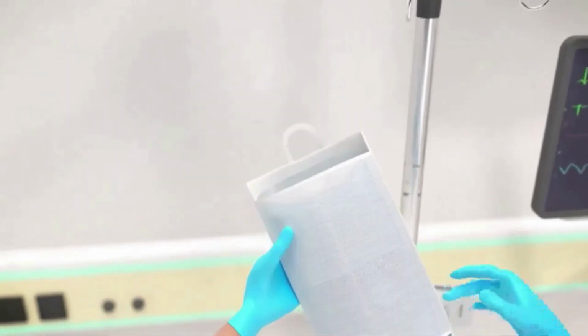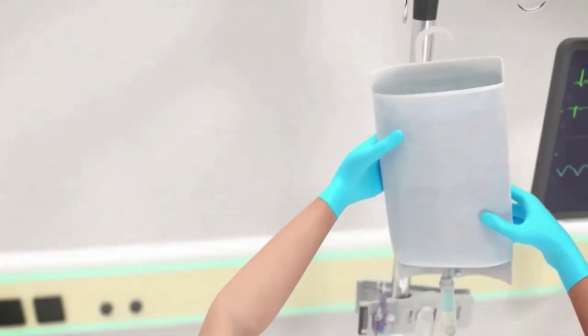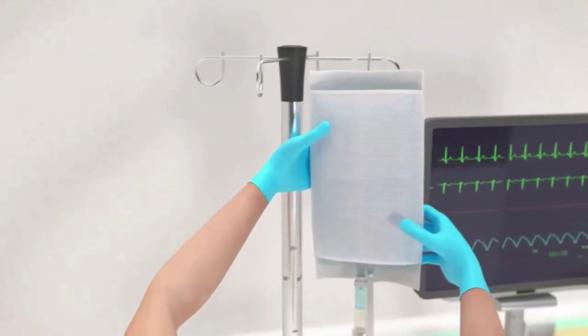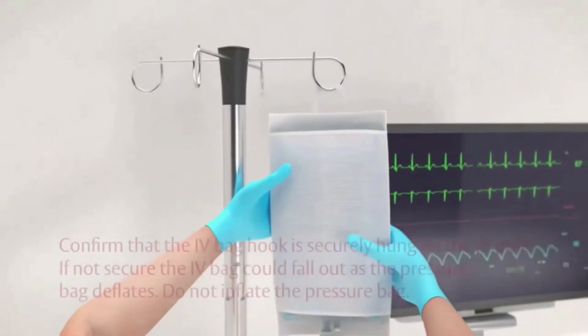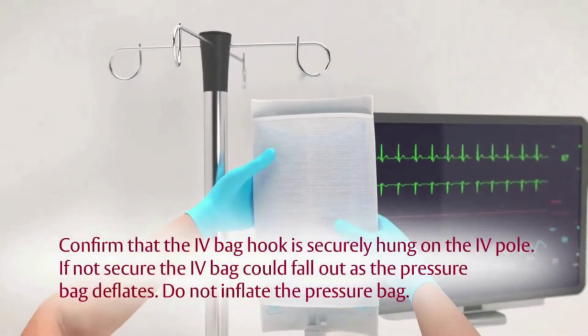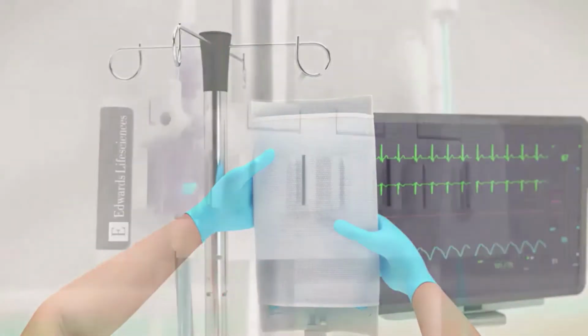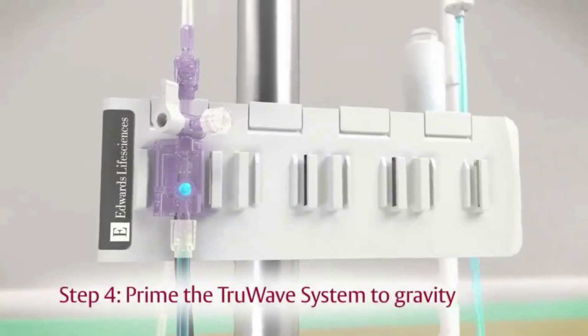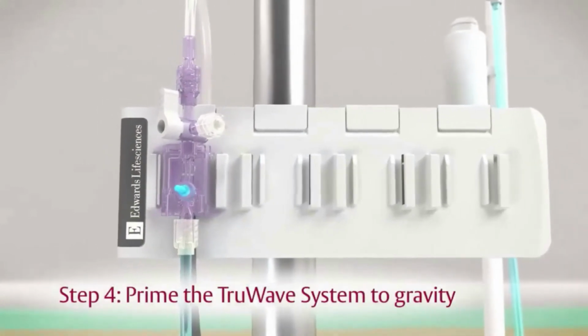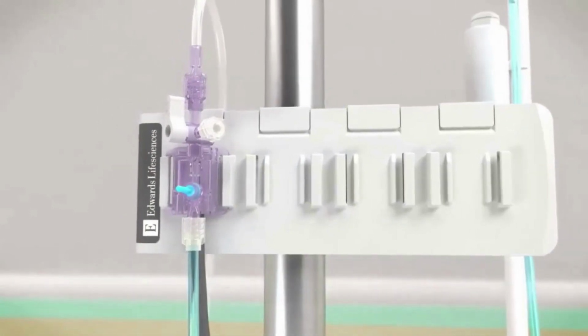Insert the IV bag into a pressure infuser bag and hang on an IV pole approximately 2 feet or 60 centimeters above the patient. Confirm that the IV bag hook is securely hung on the IV pole. If not secure, the IV bag could fall out as the pressure bag deflates. Do not inflate the pressure bag. Step 4. Prime the TruWave system to gravity to avoid microbubbles in the line.